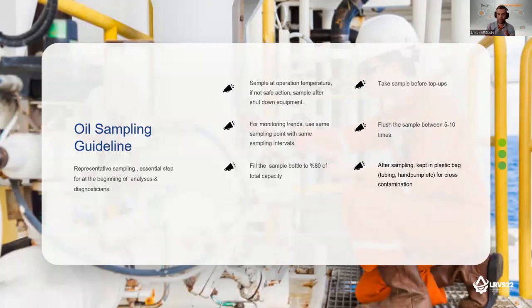This is another issue. Use sampling points with the same intervals. That's another important point, to calculate diagnostic results of future trends and detect possible failures, you need healthy data. Fill the sample bottle to 80 percent, not more, of total capacity, because that's important before preparing sample shipping to the laboratory, and when the analyst takes the sample for homogenizing and determination of oil condition. That's really important. We also had experience with leakages when shipping. Thus, we need to fill the sample bottle only to 80 percent, that's enough.